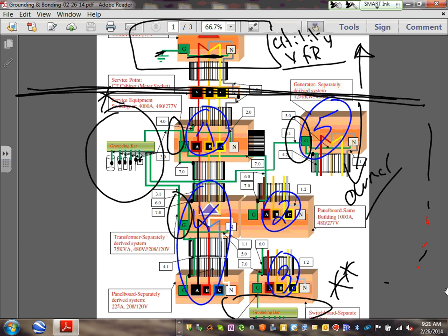So that's basically what grounding and bonding is. We talked about this one before. Again, it's not new to you guys, but this is as intensive as we can get it. I can't emphasize enough: when you establish the grounding electrode system, you can have a rod, a pipe, a water pipe, or a concrete-encased electrode foundation. Any of these will qualify, with some modification, as a grounding electrode system to tie the system to the ground.